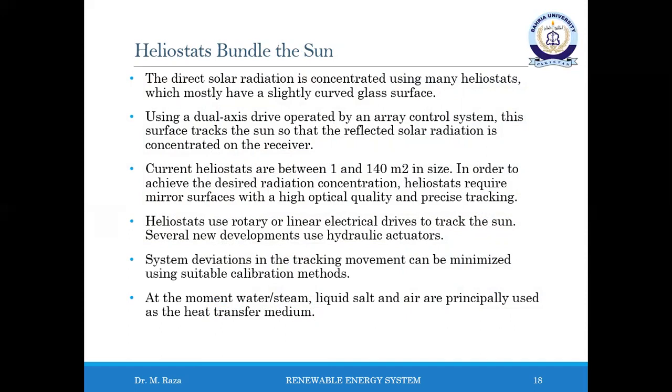At the moment, water, steam, liquid salt, and air are principally used as the heat transfer medium, whereas steam can be directly used in a steam turbine process for generating electricity. With liquid salt and air, the heat is transferred to the power plant process via a heat exchanger. The use of liquid metals or ceramic particles is currently being investigated for achieving higher temperatures as part of innovative solar tower concepts.